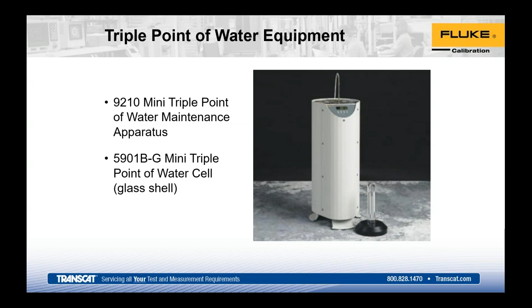Other things I've run across over the years is people not being familiar with the equipment. So education is key on how to handle them, store, transport, training your people, and then the monitoring is another piece I've seen customers fall short on when I was on the technical side. So I get some complaint, they send in a probe for Cal, it fails, send it back, hey, this is out of tolerance, and then they come back, well, when? And that's something we can't determine unless you're monitoring it constantly throughout the Cal, between Cal cycles, I should say.